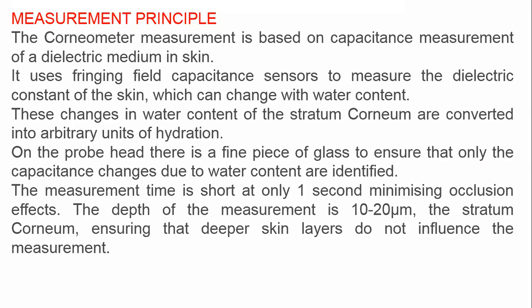The principle of the corneometer is that it measures skin hydration by utilizing capacitance — specifically, it measures the dielectric constant of the skin using fringing field capacitance sensors. The dielectric constant of the skin changes with the presence of water content. As the water level is minimized or increased, the dielectric constant changes. The changes in water content of the stratum corneum are converted into arbitrary units of hydration, and that dielectric constant is measured as capacitance by the sensors.